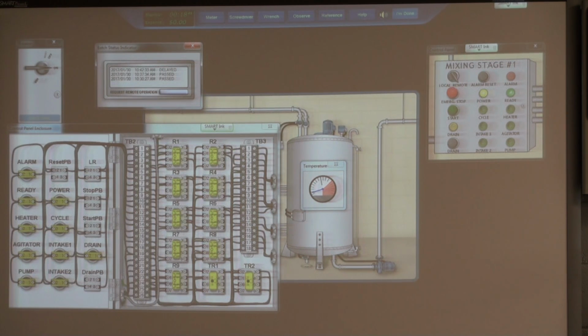So I have to go back, and that's why I say if you ever replace one of these timers, they come off the shelf with a preset time. You better make sure they go back to the time prescribed inside of your manual there, or you're gonna set them out. First one was closed.